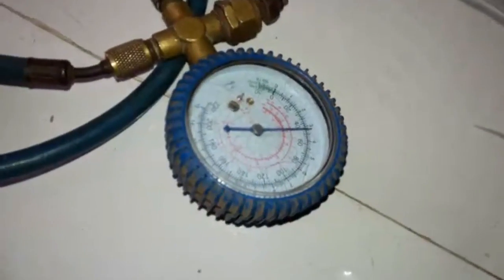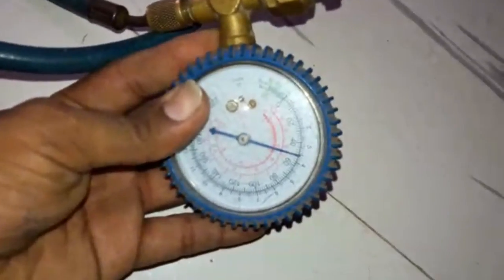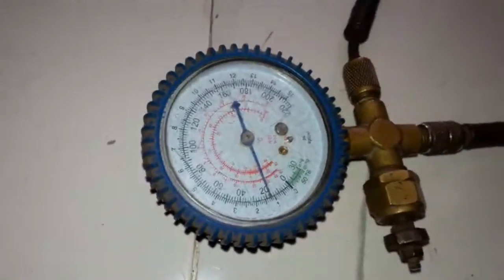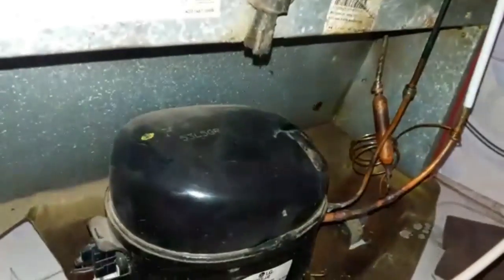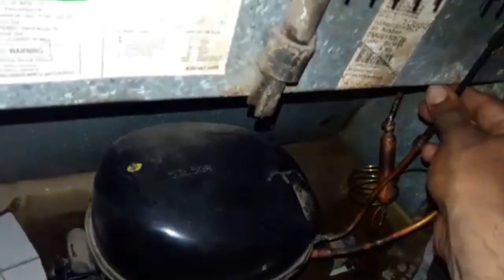We will refill the refrigerant up to 50 to 60 psig. Now switch on the power supply of the refrigerator and keep watching the gauge. The suction pressure should be 10 psig. The discharge line will be very hot. The starting of the condenser is hot and the lower part of the condenser is warm. The filter is also warm.